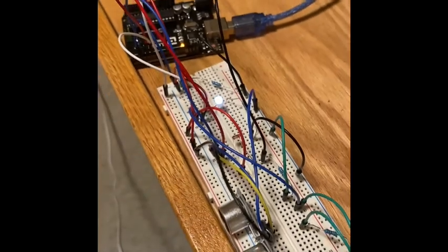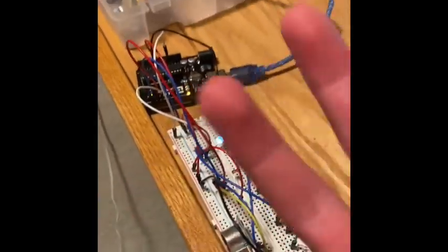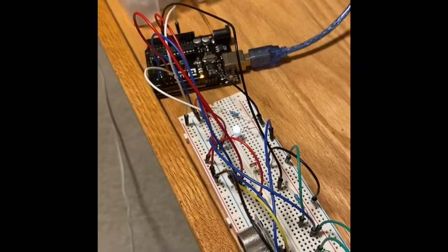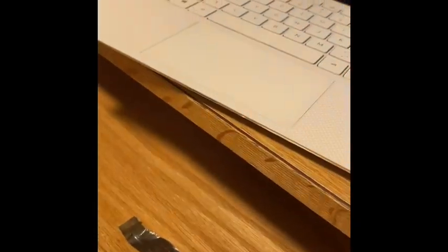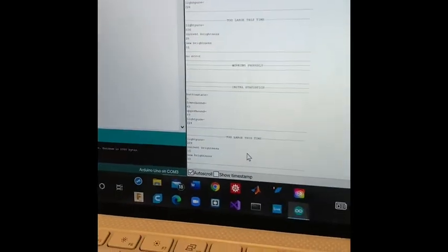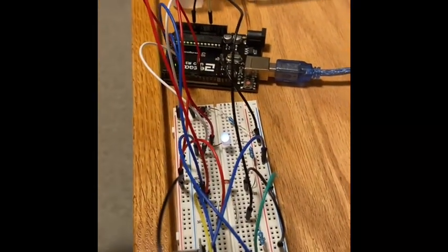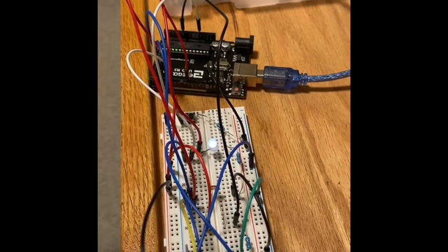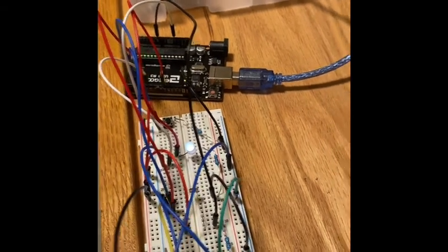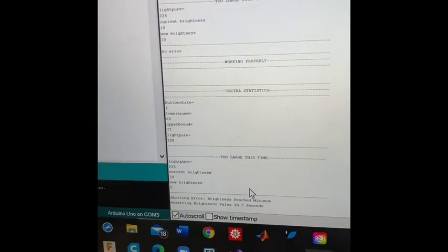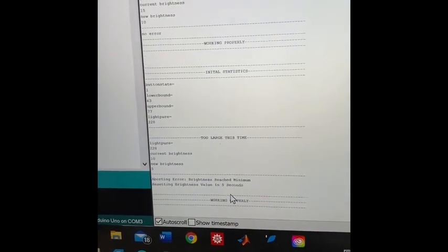So it's at 20 right now. It's very clearly lighter. I could probably put this on and it's not like blaring the screen. I no longer have to show full exposure. It's at 10 right now. 10 brightness value. And as soon as it gets below 10, which it's at 5 now, again, I have a 5 value tolerance on this one, similar to the last one, it gives an abort value.